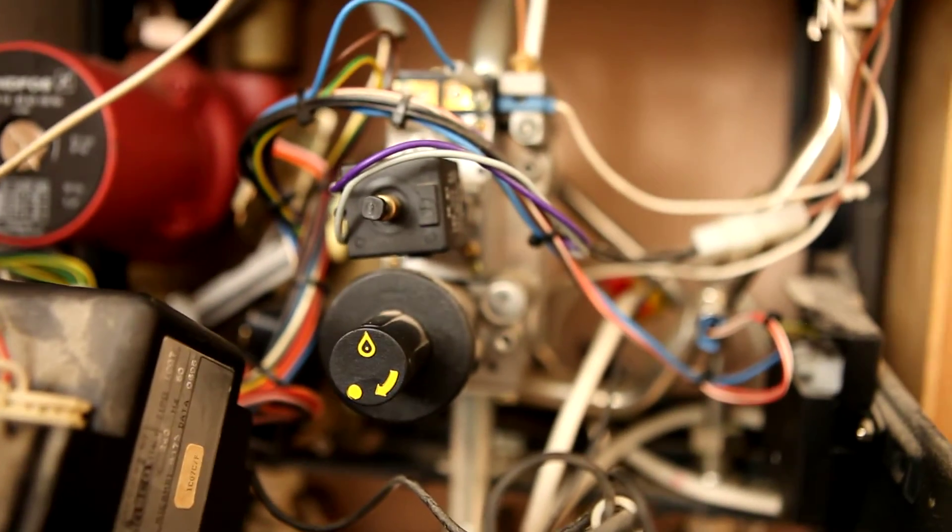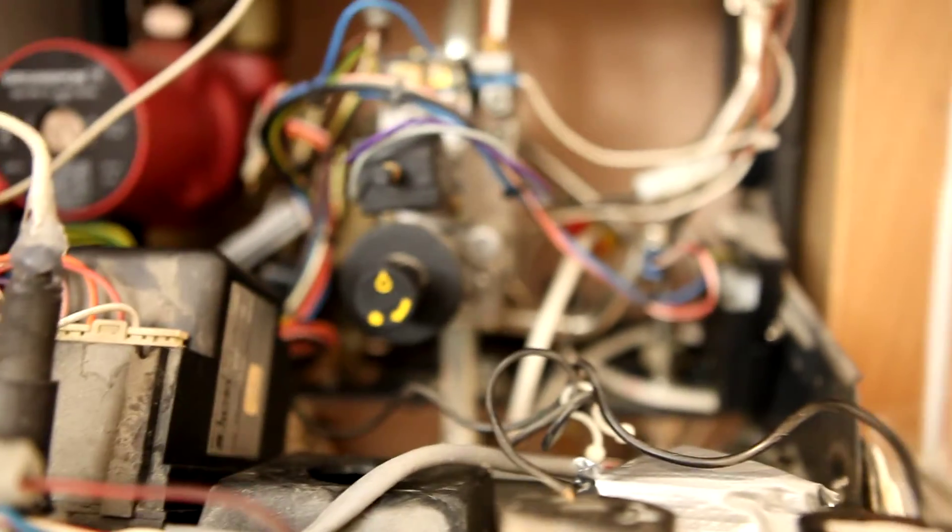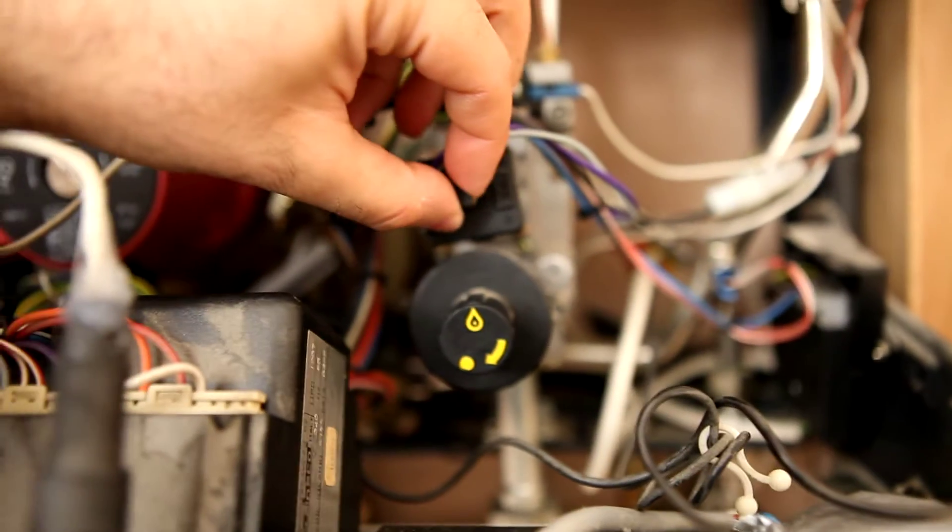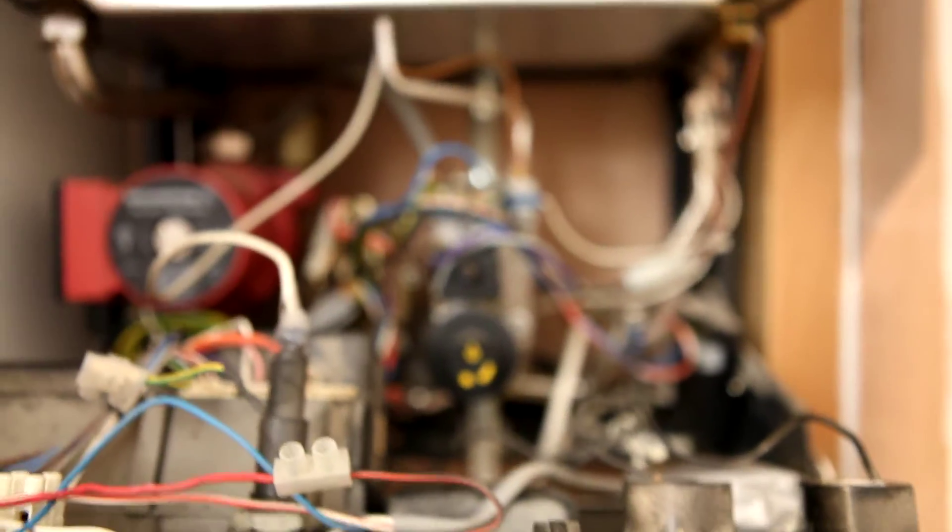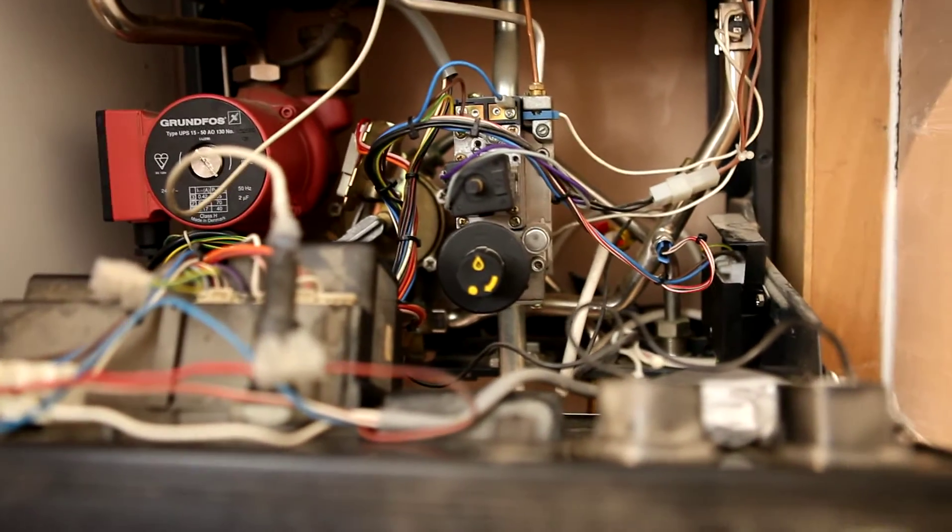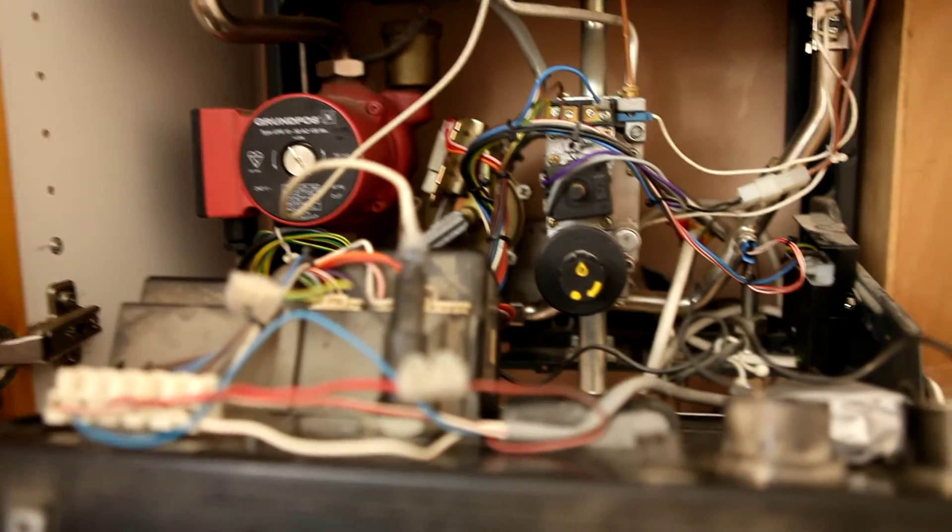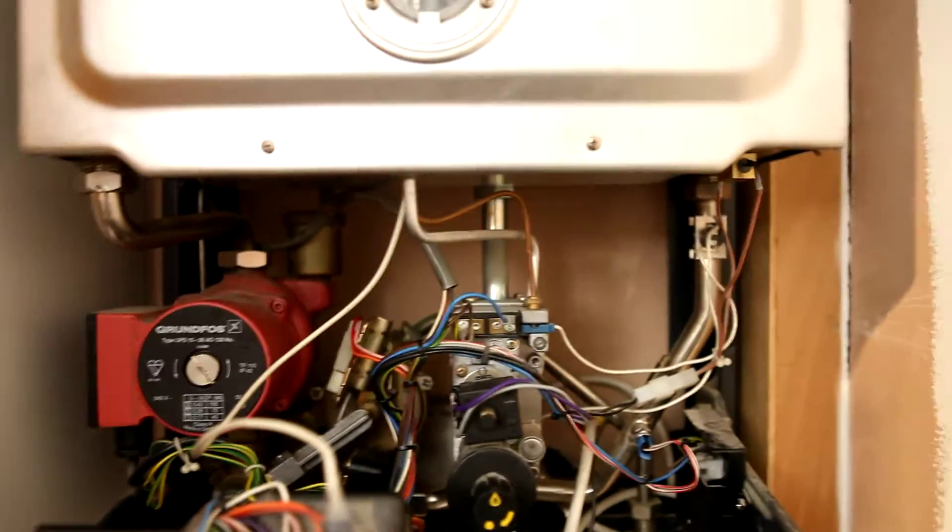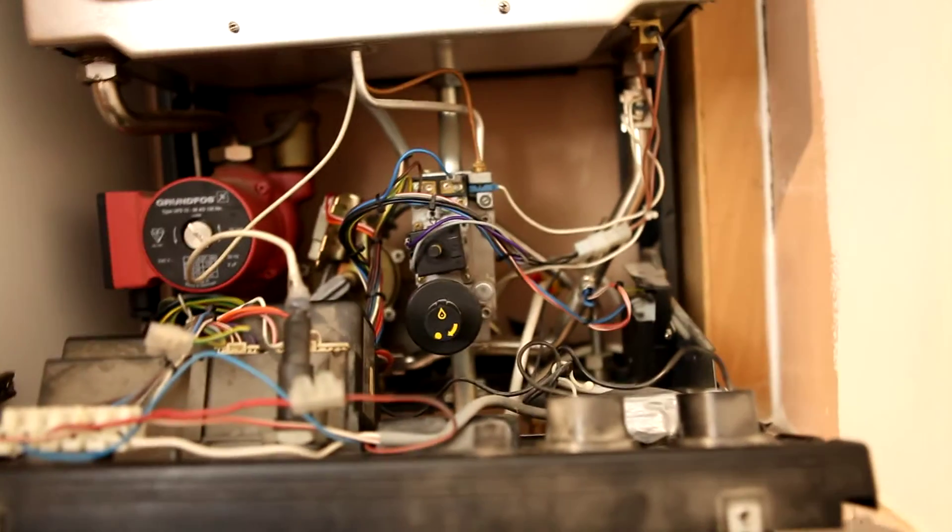Okay, gas valve problem. So I take the solenoid off, and sure enough the gas pressure stays on full, so it's actually a gas valve problem. Let's have a look at it. In the front here is a little adjuster knob, and guess what? This is the adjuster knob for minimum gas pressure, and guess where it was set to? Maximum. So we've had three gas engineers come round to check this boiler. I even told them what the problem was in detail. I told them that the gas valve is not modulating, and no one could find this problem. So in frustration after having three half days off work, I've come home, and I've taken this boiler apart, and it took me about five minutes to identify this problem. I've adjusted the gas pressure, and now it works beautifully.